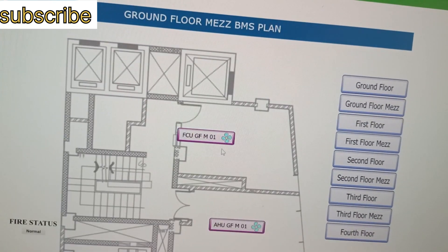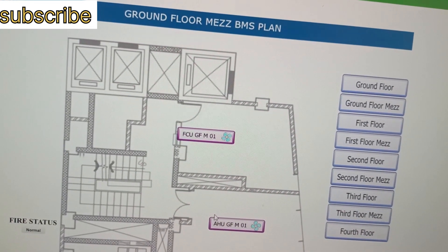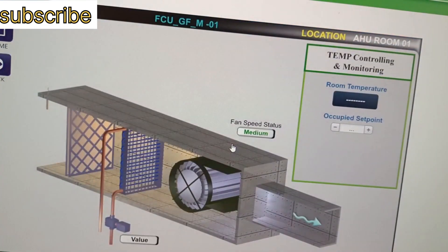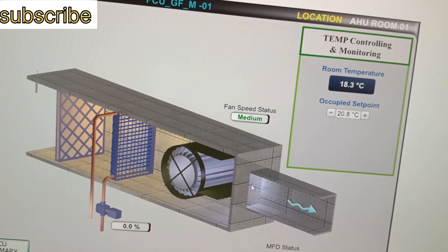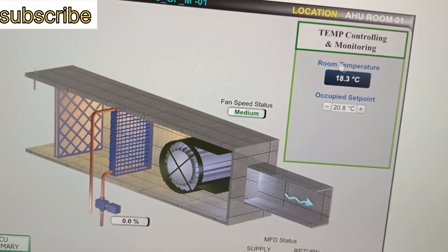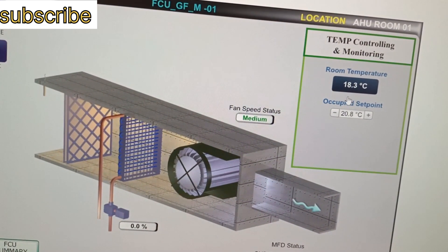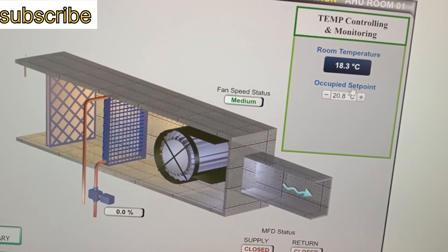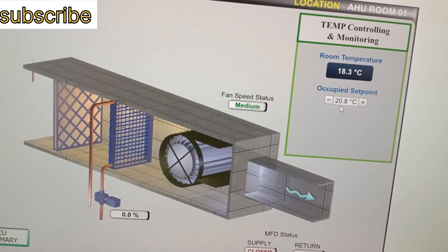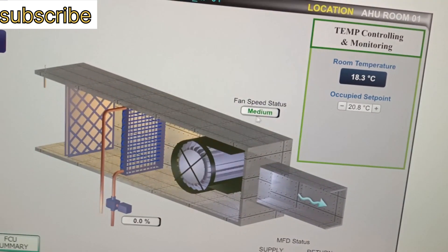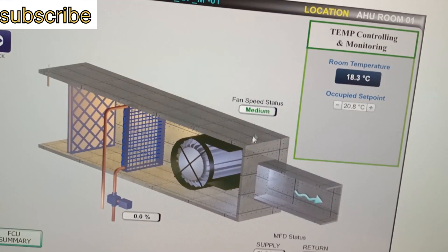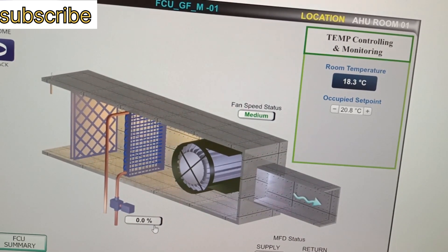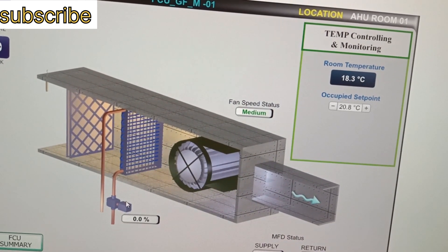On the ground mezzanine we have two FCUs, one is showing running status. Here we have temperature control and monitoring — the temperature showing is 18.3 degrees Celsius, occupied set point is 20.8 degrees Celsius, fan speed status is medium, and the chilled water valve is showing 0.0, so maybe it is in off position.